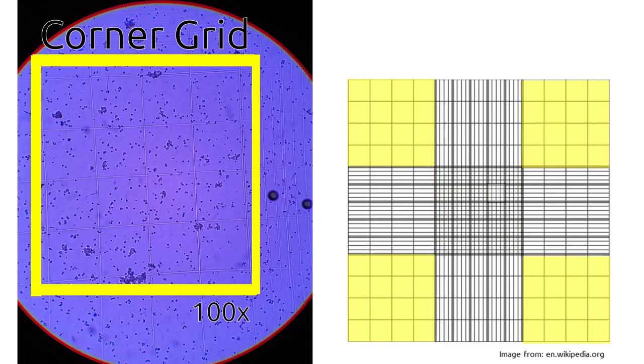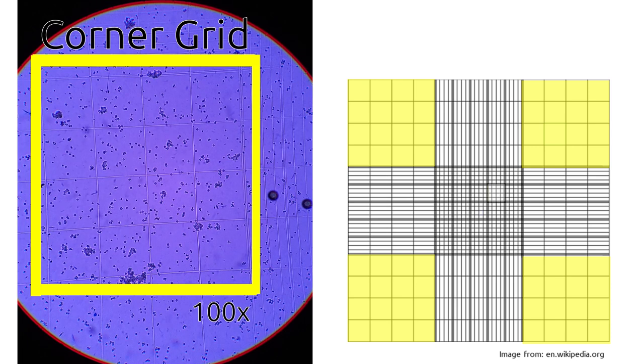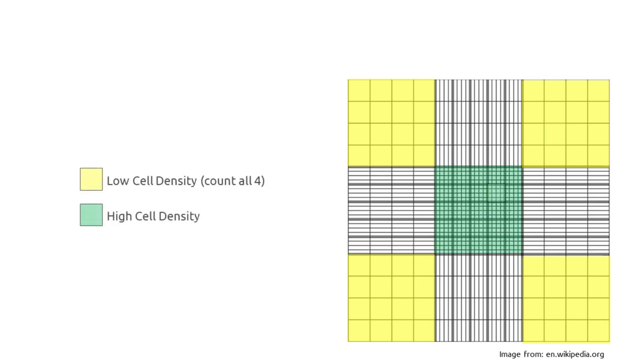The second region is actually four parts of the coverslip. It's the four corners. Each of these corners is one millimeter by one millimeter in size and has a lower density grid, typically 0.25 by 0.25 millimeters. So this is perfect for counting lower density solutions, but because you're counting a smaller number of cells you should count all four corners in order to ensure an accurate count.